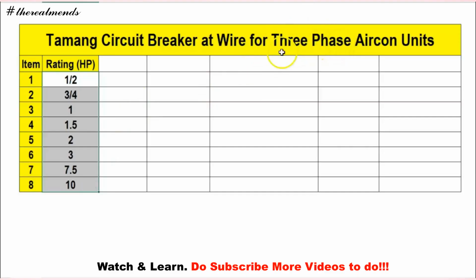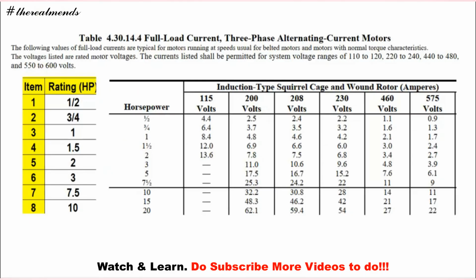And then to proceed, so we need to size yung magiging circuit breaker for this particular aircon unit. So refer to the PEC 2017. Okay, that's from table 4.30.14.4, full load current 3-phase alternating current motors.